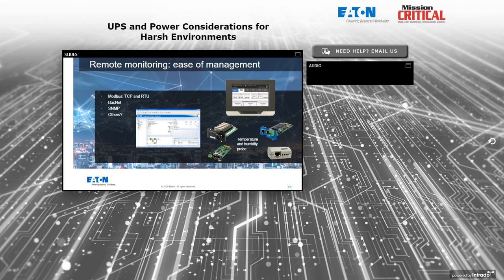It might be BACnet, it might be Modbus, it might be SNMP, it might be just dry relay contacts that can be programmed. That kind of communication capability, you want to be able to say yes to however the client wants to communicate with their machine. So the end user may have a particular device or a particular type of building management system. The UPS needs to be flexible enough to talk to that and provide useful information. And one of the other things you see in the lower right-hand corner is a temperature and humidity sensor.